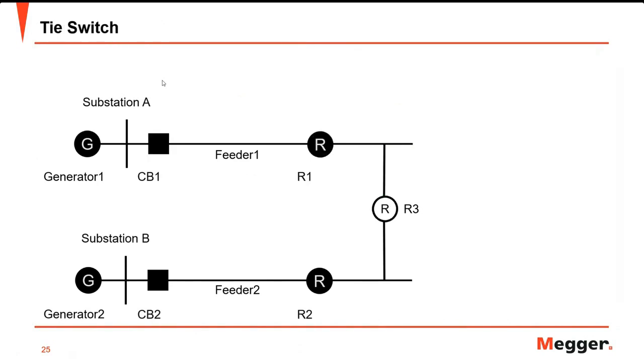Tie switch: another advantage of line reclosers is that some of them have voltage transformers on both sides that can be used to check synchronism. Suppose circuit breaker one is under preventive maintenance — the recloser can be used to check synchronism between feeder one and feeder two prior to tying the two together.